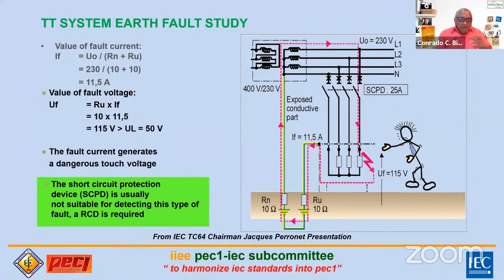So we can, even the IEC have decided, nakita nila to, 50 volts sa AC and 125 volts sa DC, no, yung safety voltage. And the same with UL or the American side, 50 volts din. Kasi isa lang naman yung katawan natin, so pare-pareho yung voltage, ang importante na makontrol natin dito. Okay? So ang requirement sa TT system, the short circuit protection device is usually not suitable. Kita naman natin, ano? So, mandatory talaga yung RCD, residual current device, ang kailangan natin dito sa TT system.